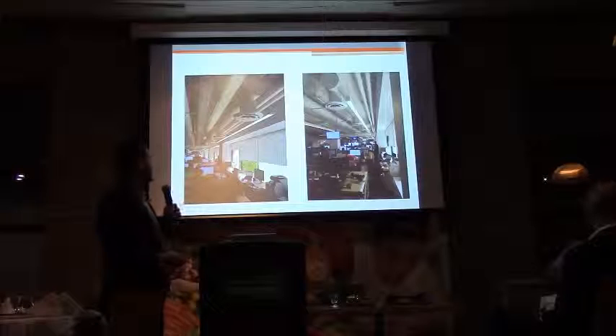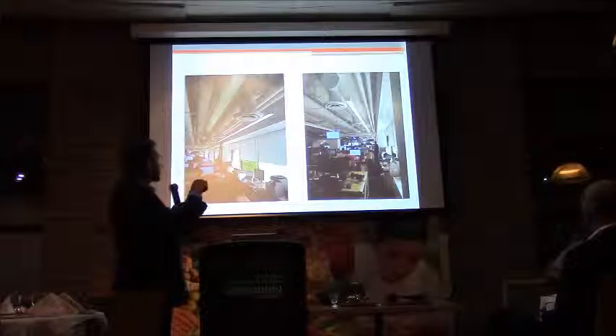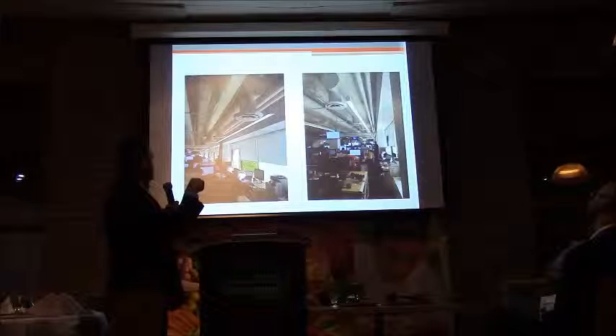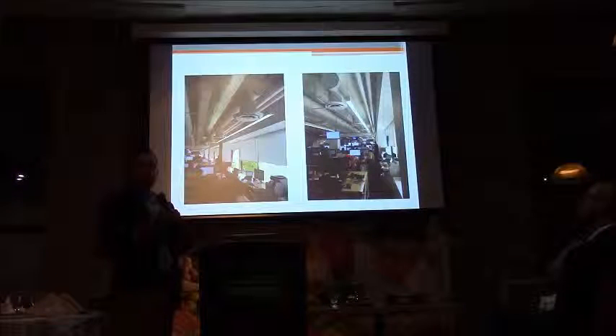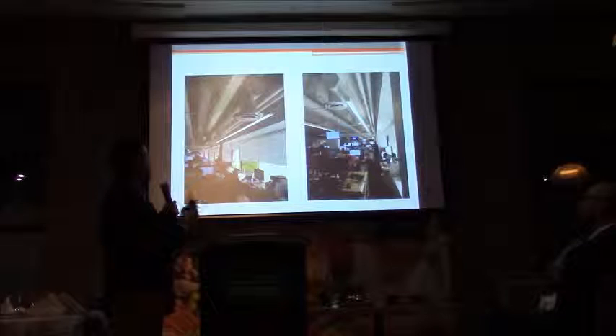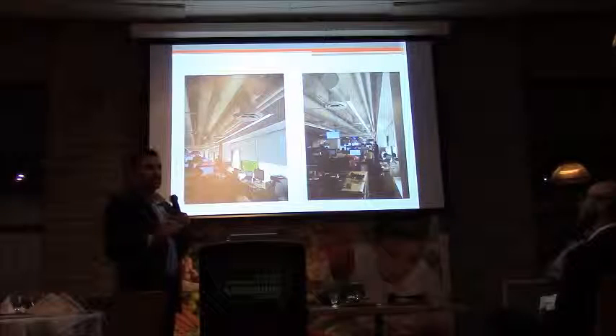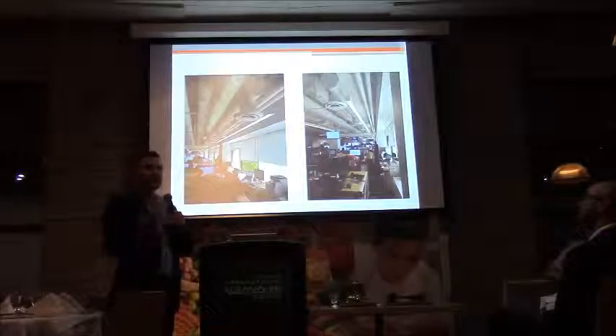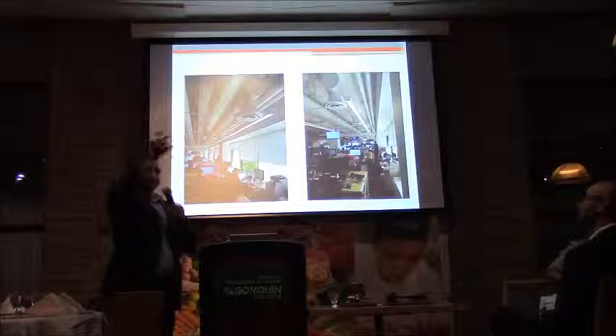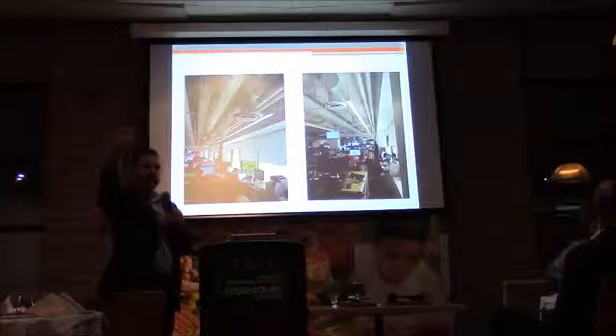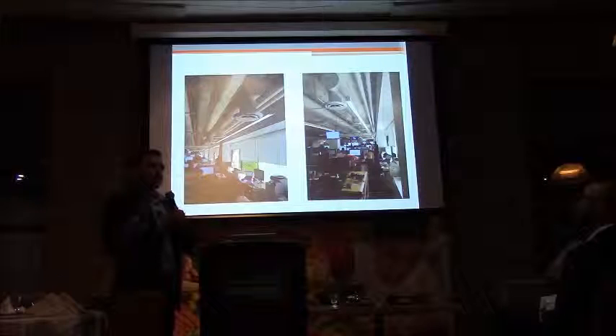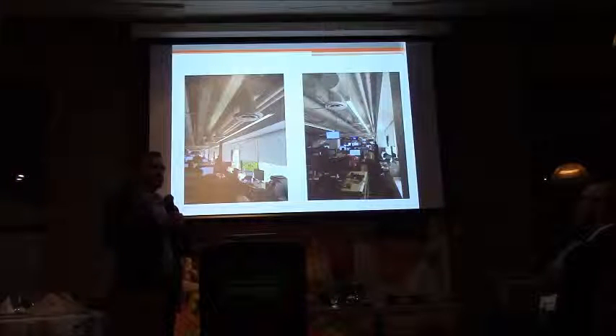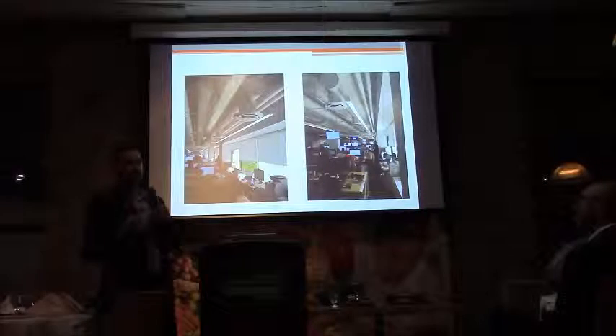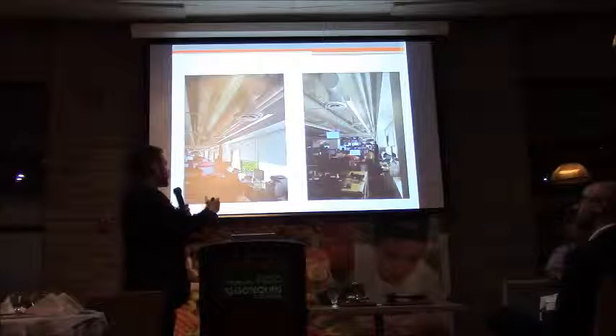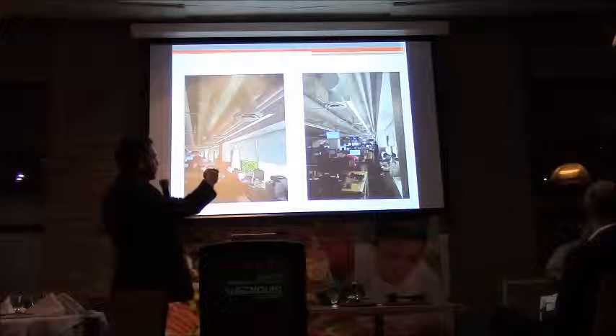We proposed a high induction diffuser. The first thing to notice is that they're using those standard cone diffusers. And they're good diffusers. I'm not bashing the cone diffuser. It is a very good diffuser. But the cone diffuser needs a ceiling because of the Coanda effect. You need a ceiling so that the air, once it leaves the diffuser, sticks to the ceiling, so that when it reaches the occupied zone, the velocity is lower and the temperature is closer to your set point temperature. So there are two mistakes here: you're using a cone diffuser for variable air volume, and you don't have a ceiling.